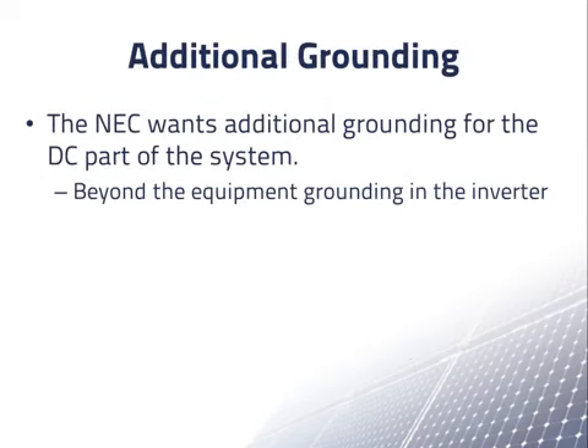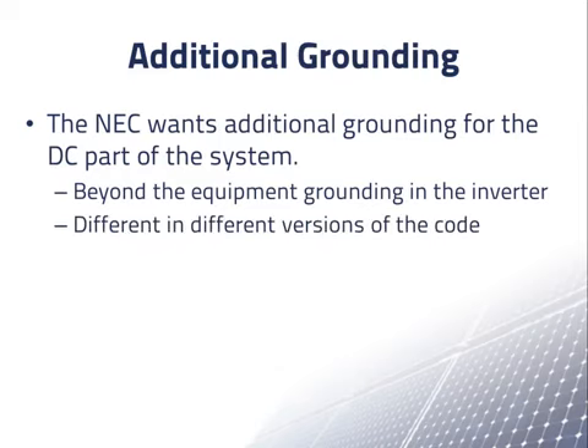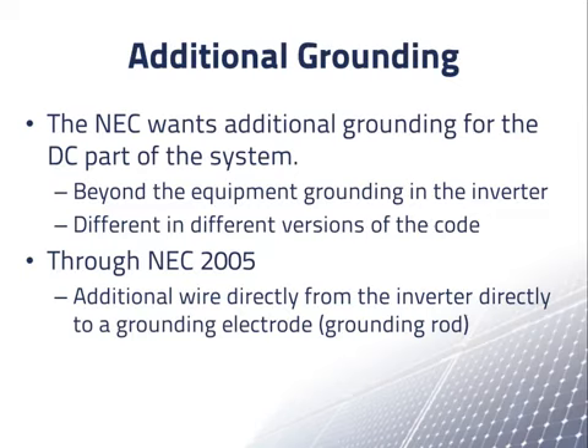In addition to this normal grounding, which is what one would find for any exposed electrical equipment, the NEC also wants an additional connection to ground for the equipment on the DC side of the system. This requirement can be somewhat confusing because it has been different in different versions of the NEC. The simplest requirement was up through the 2005 NEC. In this case, the NEC simply required an additional grounding wire going from the inverter directly to the grounding rod, but this was changed in most recent versions of the NEC.